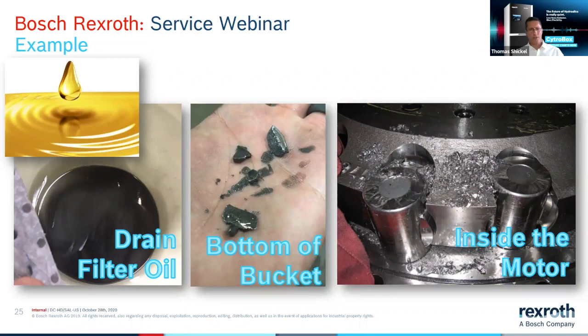So again, just to highlight the importance of having good clean oil, it's always very important to start with a brand new oil base. A lot of times we found some OEMs that have complained about dieseling oils, and that's been the result sometimes of them trying to cut corners and using some older reconditioned oil stock. And the problem there is it's a little more challenging to maintain the oil preservative packages. And if that preservative package were to drop off very quickly, the oil will start to increase in acid number, begin dieseling, oxidation. And again, you immediately start attacking your components, and you'll see a change in color in a matter of hours, and then you'll start having the components start to break down.